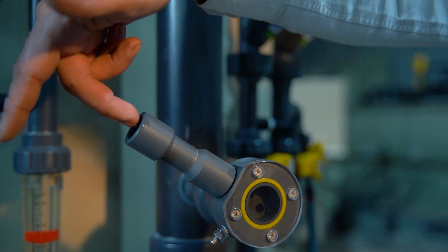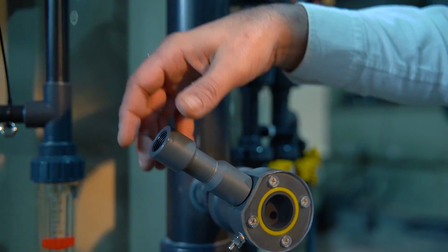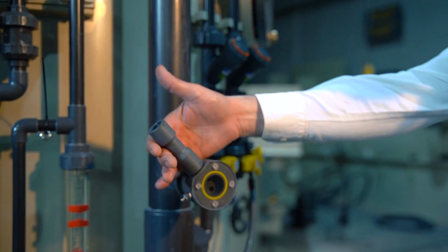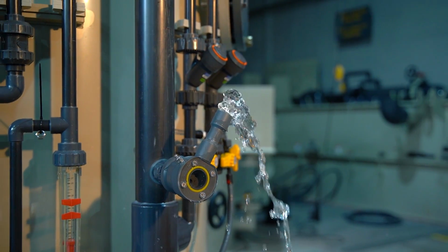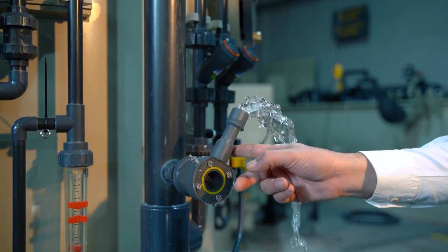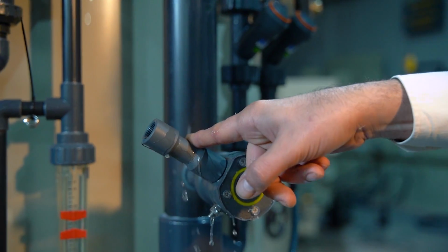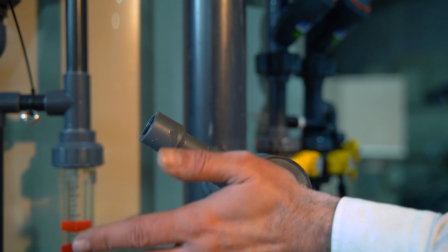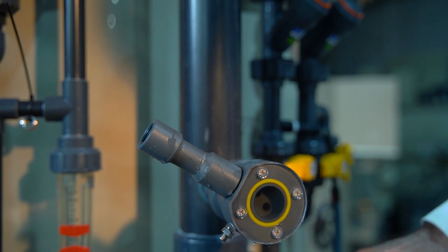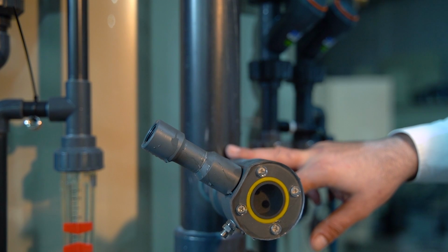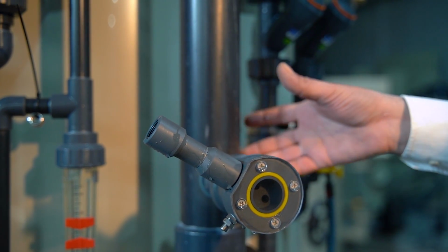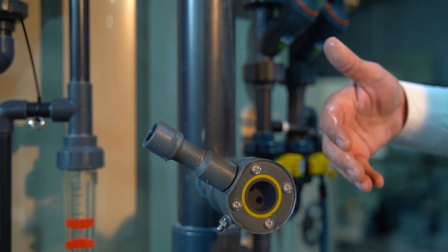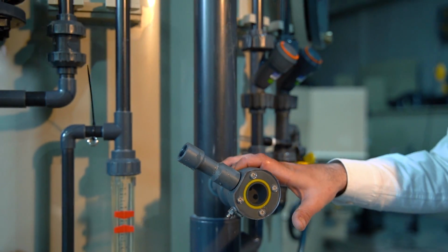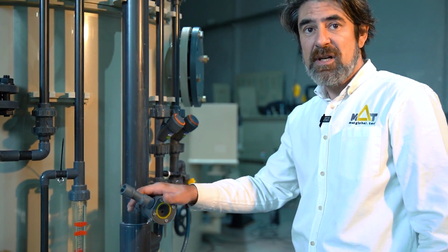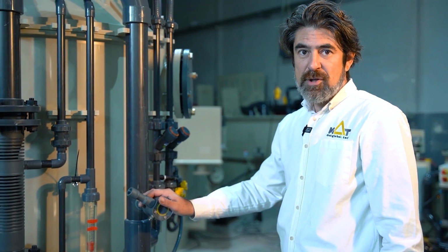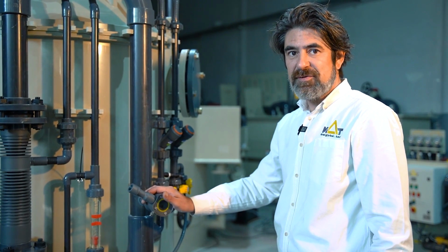Let's assume I install another probe or I clean my probe and put it back. Then again I smoothly turn it. Now again we have the water flow. So this lets us do all kinds of service or manipulation on the probes while we have pressurized running water inside the pipe. And imagine if this pipeline is 500 millimeters in diameter and many meters long, we are talking about draining so many cubic meters of water just for a single probe change. So this is the biggest advantage of our dry tap unit.